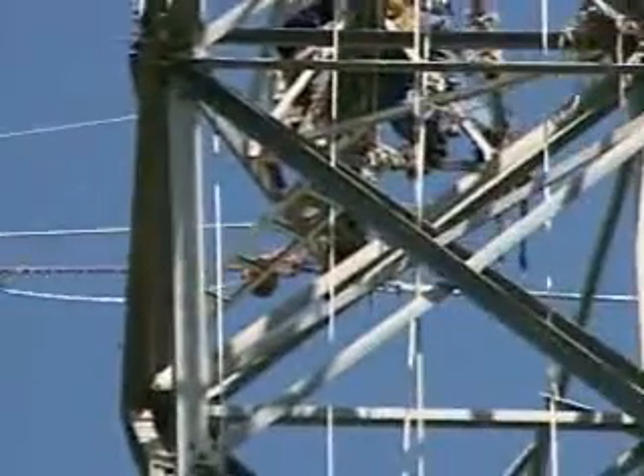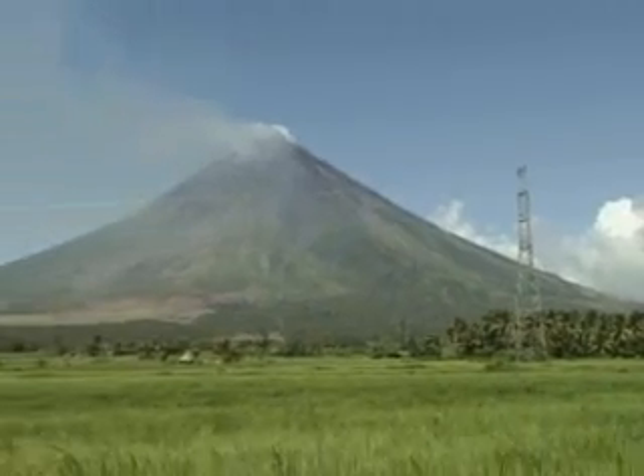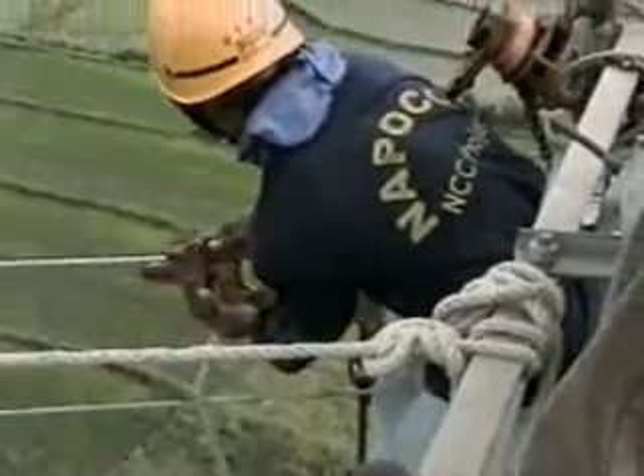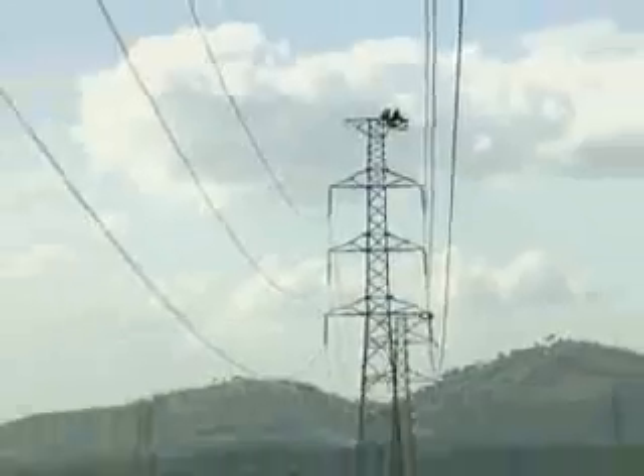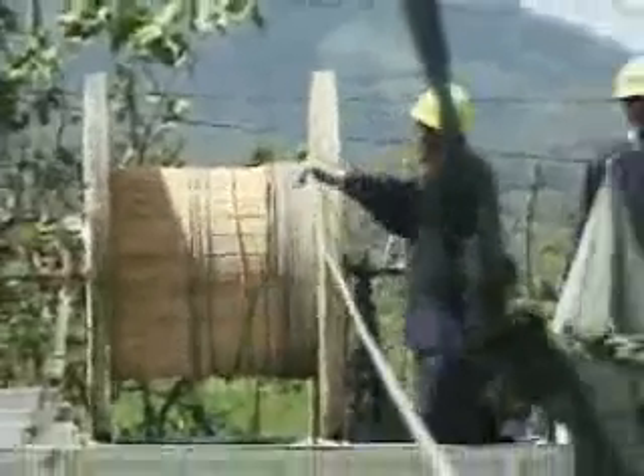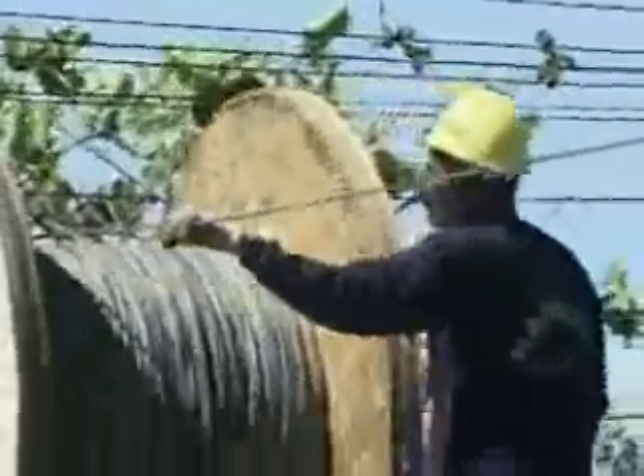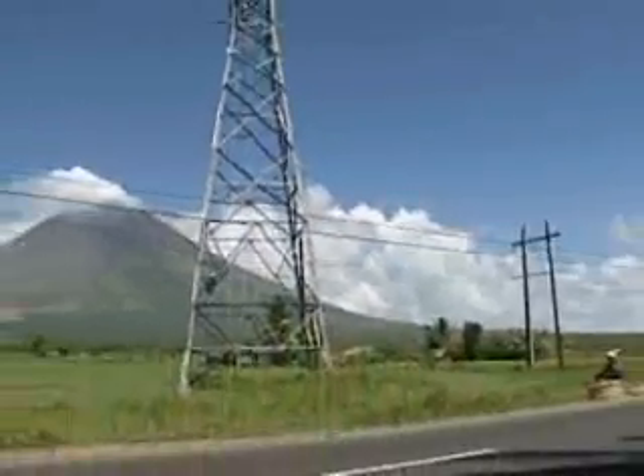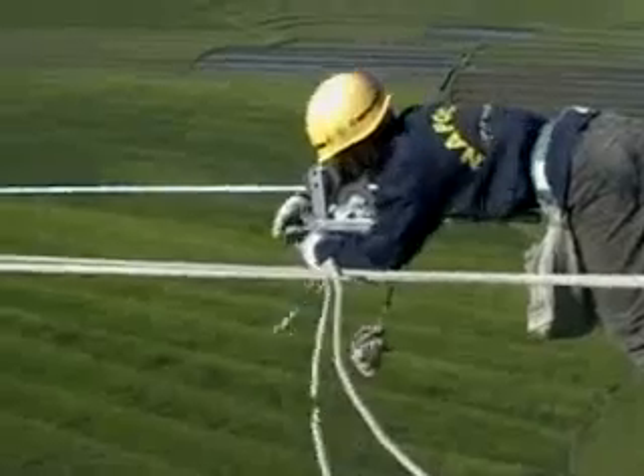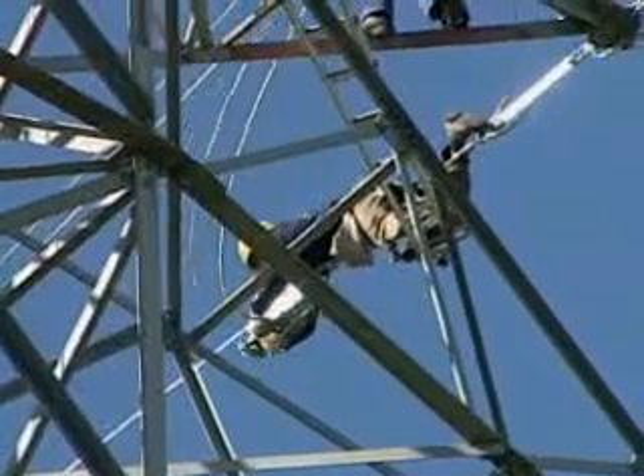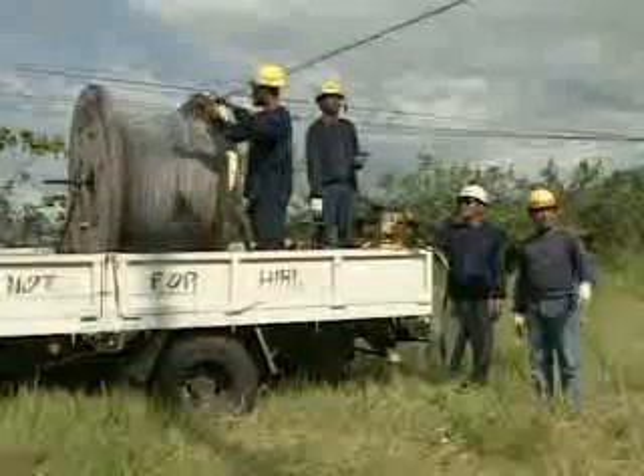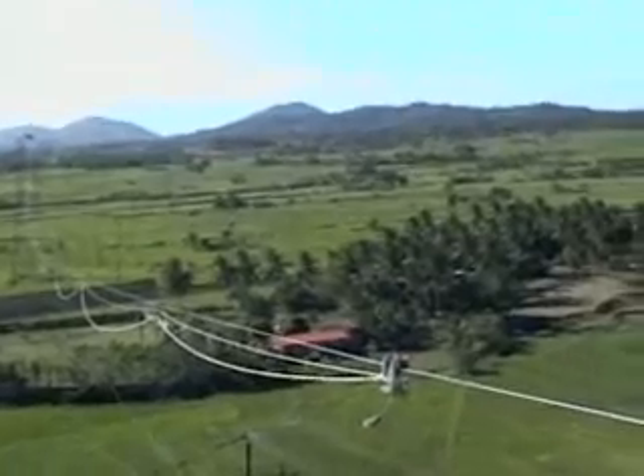A tail rope, which is similar to the insulated rope, with an equivalent length of 1.5 span, is connected to the last end of existing ground wire. The come-along and the lever block are attached to the OPGW in every intermediate tower to ensure that the dismantling is secure. The existing ground wire is then pulled out towards a reverse direction using a winch or reel winder. When the end of the tail rope reaches the OPGW, a braking machine is fixed onto the OPGW, and the tail ropes as well as the setting rope are attached to the braking machine. The pulling out of the existing ground wire continues, and for every span that the braking machine will pass, the setting rope and the hanging pulley blocks are dismantled.